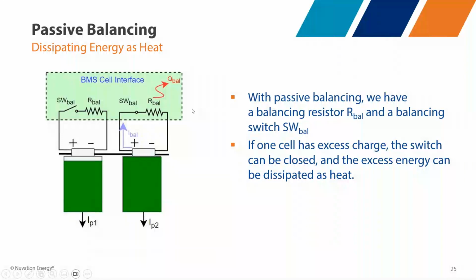Passive balancing is a pretty simple system. You have a switch that is a balancing switch per cell, and then you have a balancing resistor per cell. In this case, where cell 2 is full, we would close this balancing switch and dissipate excess energy as heat. That would give this cell a little bit more room, and then you can apply more charging to the entire stack, bringing cell 1 to a full charge.